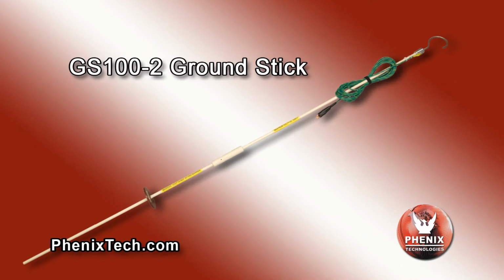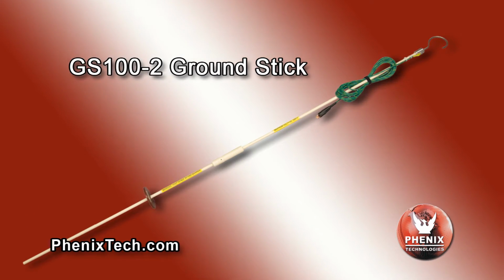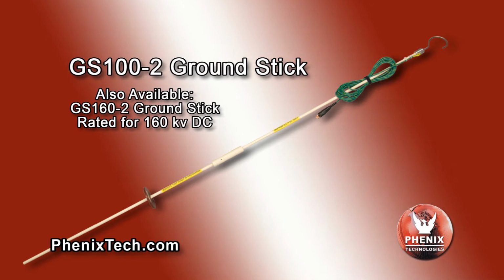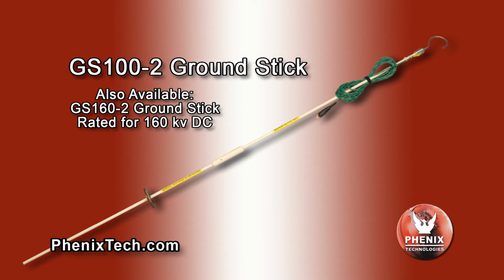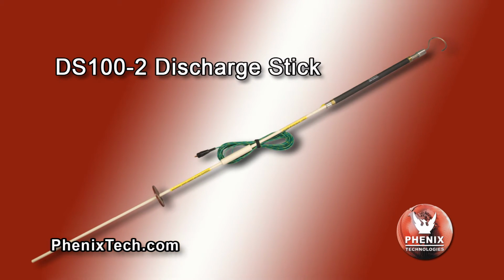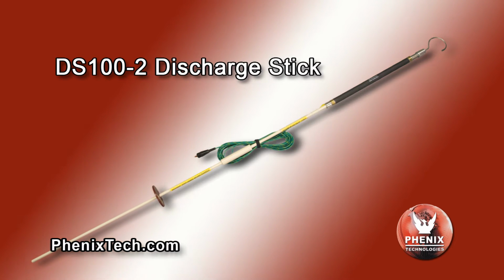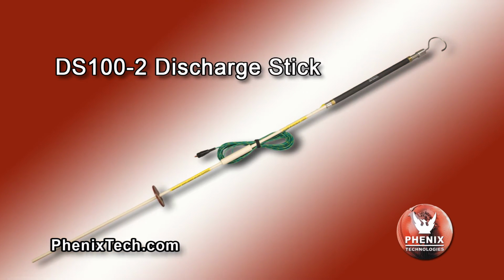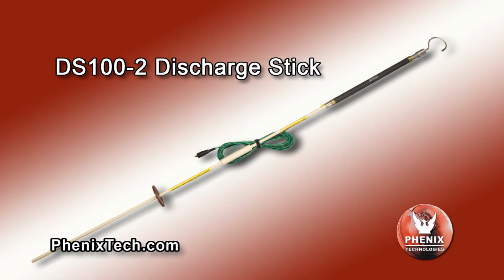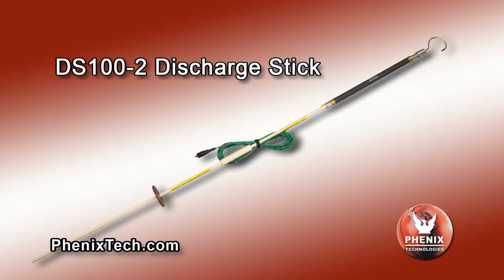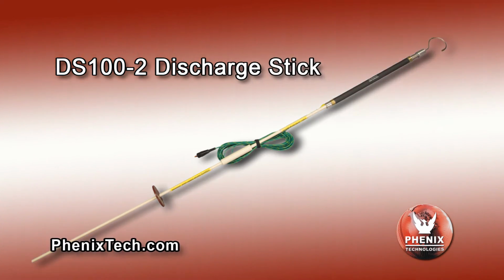The model GS100-2 ground stick is used for grounding relatively low capacitance test objects, such as insulators, switchgear and motors. The model DS100-2 discharge stick has a resistor in series with ground to bleed the charge from higher capacitance test objects in a controlled manner, such as shielded cables.